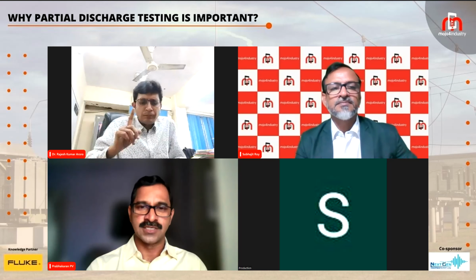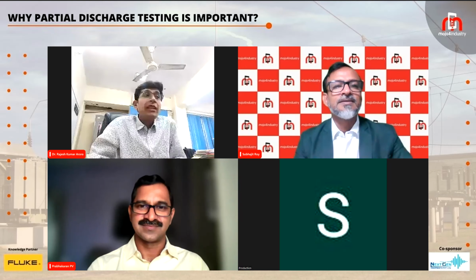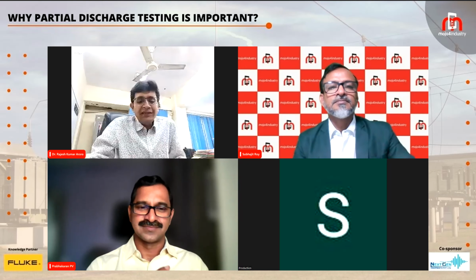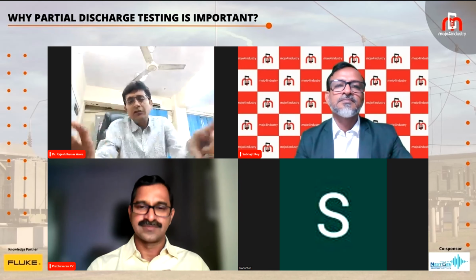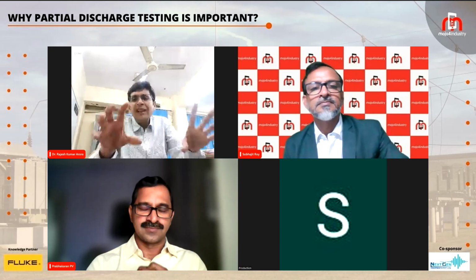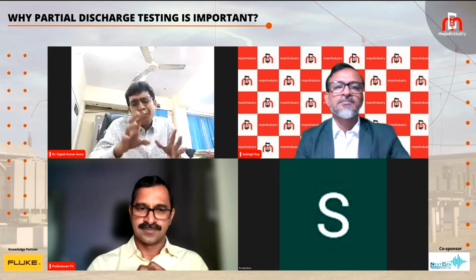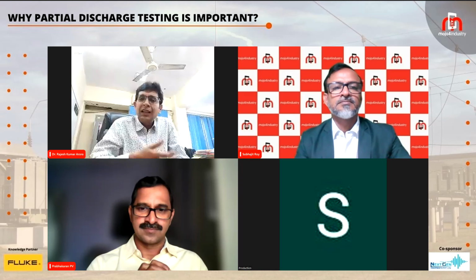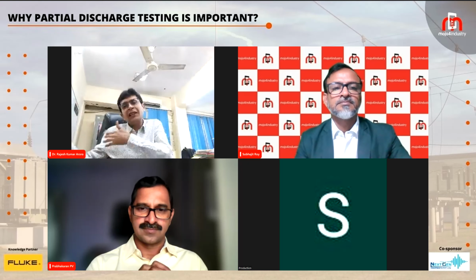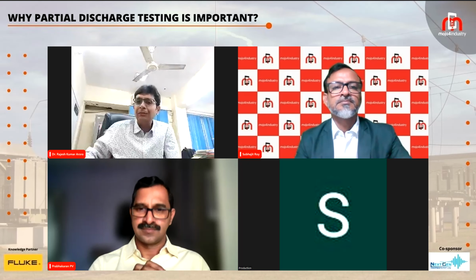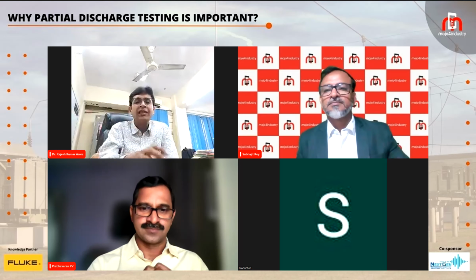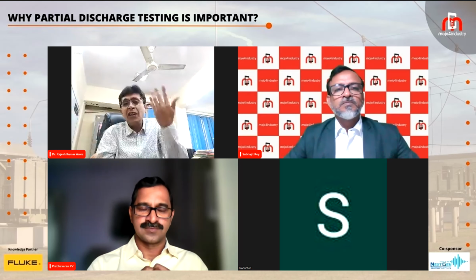Dr. Arora, I think you've already done something like that. Yes. In many utilities, when you notice that a particular section of your GIS is giving frequent PD troubles, we fix sensors there permanently, making it an online system, and for other parts we stick to the offline system. That's a kind of hybrid, where for the same utility some part is online and some part is offline, depending on the nature of the fault, the location, and the load conditions.